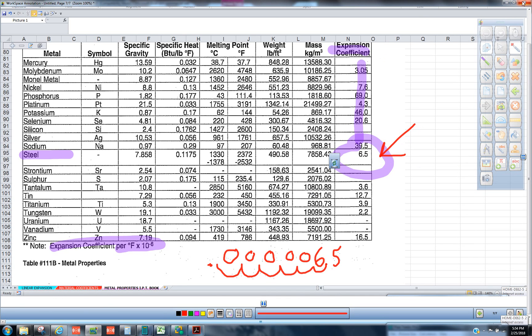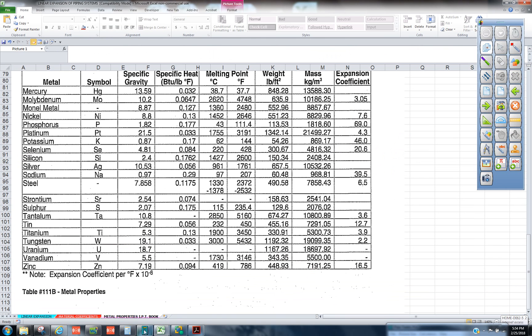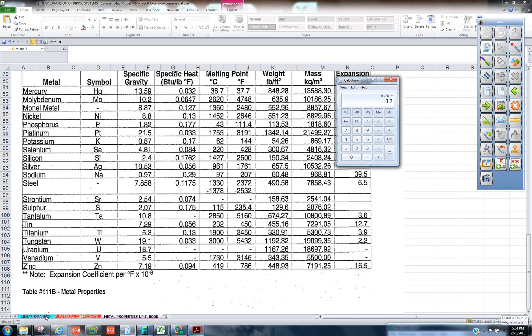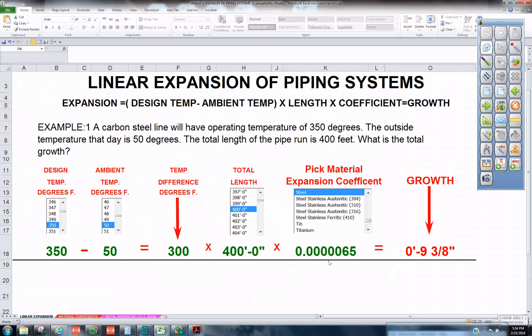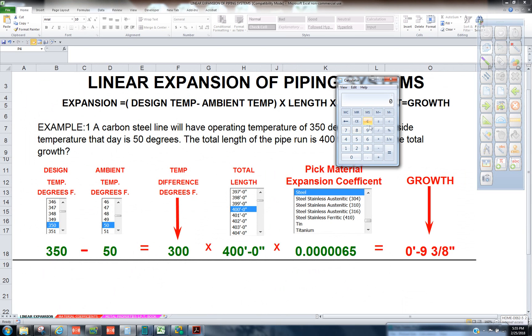So when we get our calculator and we apply the formula, we take the temperature difference of 300, times it by 400 feet, and then times it by 0.0000065.